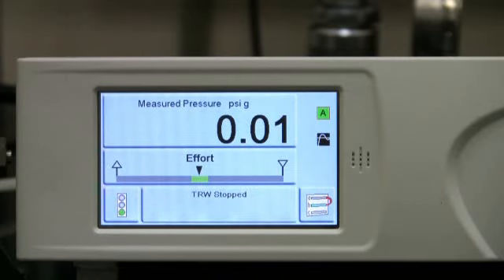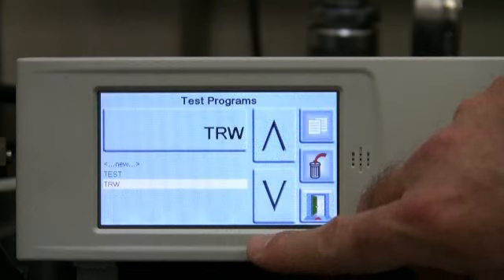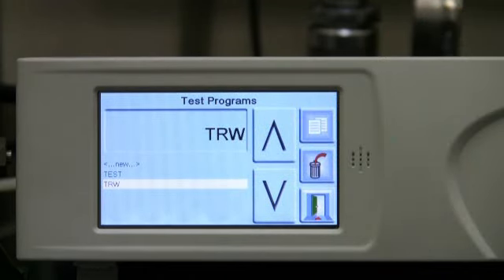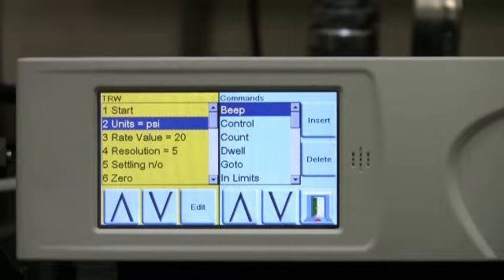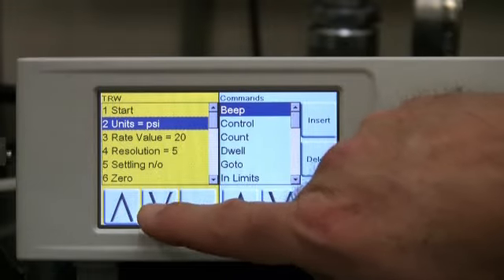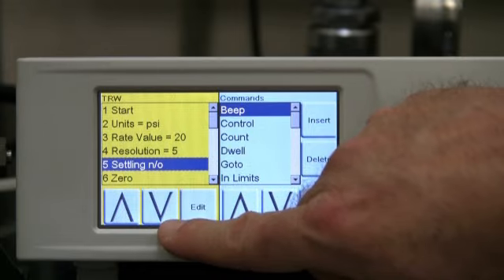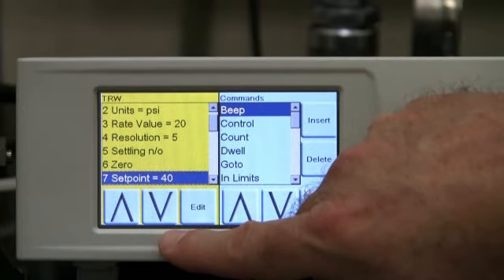Although PACE5000 is provided with RS-232, IEEE 488, and USB remote interfaces, and is compatible with Intecal Advanced software, the test program task provides an increased level of automation when not using a PC-based setup. Up to 100 programs can be stored in PACE5000. Each program can have multiple steps and perform various functions. For example, in this program, the units are first set to PSI, the control rate is set to 20, the pressure resolution to 5 digits, and the slew rate to no overshoot. The unit will then perform a 0 before controlling to the first set point, which is 40 psi.